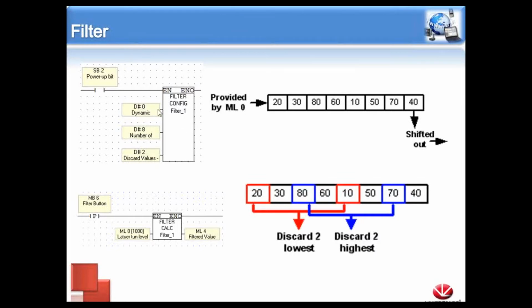The first is if you want to do a dynamic average or an order-weighted average. What that means is for a dynamic average, each value is going to have the same weight in the end result. Whereas with the order-weighted, the newest values have more significant weight than the oldest values. So if you imagine a FIFO system, the value that's about to be erased is not as significant to the average as the newest one.